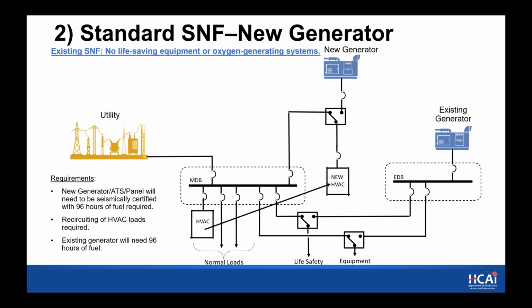For the new HVAC systems, or for the HVAC equipment that's transferred to the new transfer switch backed up by the new generator, that would need the 96 hours. So the assumption here, and this would have to be verified with the facility assessment form, is that if you don't have any life-saving or oxygen generating equipment, then all you would need to do is transfer the existing HVAC loads to maintain temperature to the new system, and that would need to have 96 hours.